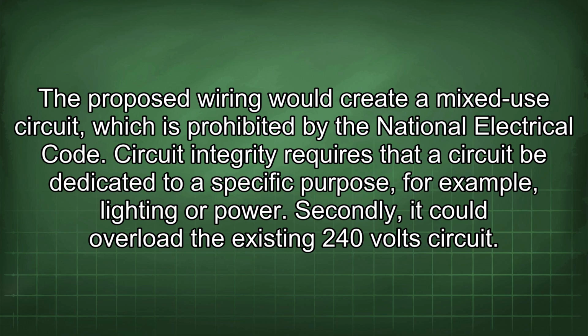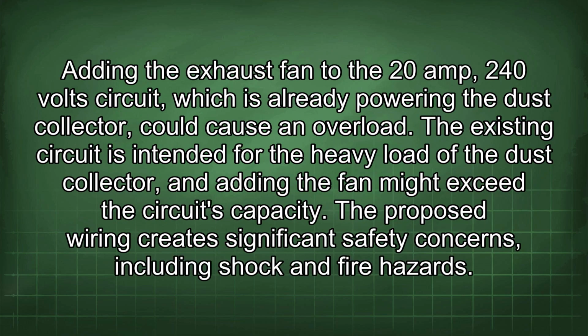Secondly, it could overload the existing 240-volt circuit. Adding the exhaust fan to the 20-amp 240-volt circuit, which is already powering the dust collector, could cause an overload. The existing circuit is intended for the heavy load of the dust collector, and adding the fan might exceed the circuit's capacity. The proposed wiring creates significant safety concerns, including shock and fire hazards.